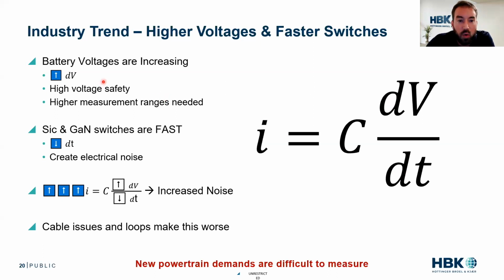What does this mean? Battery voltages are increasing, so when the inverter switches on, that change in voltage increases, giving a higher dV. We also need higher voltage safety and measurement ranges for amplifiers. We're seeing a push to silicon carbide and gallium nitride for faster switching frequencies since inductances are lower, avoiding some current ripple. The real benefit of SiC and GaN is that they turn on and off extremely quickly, lowering the dT. So we have a raised dV and a lower dT, which creates electrical noise.